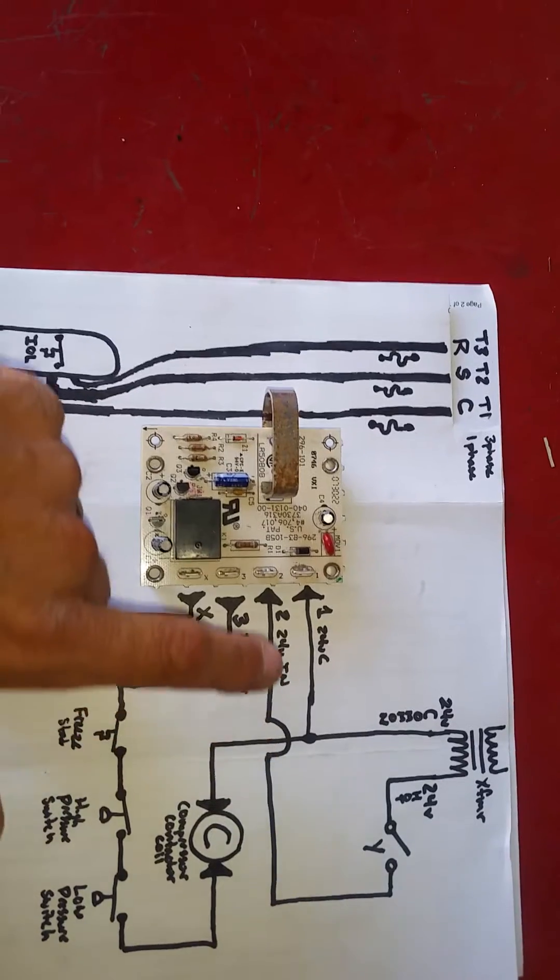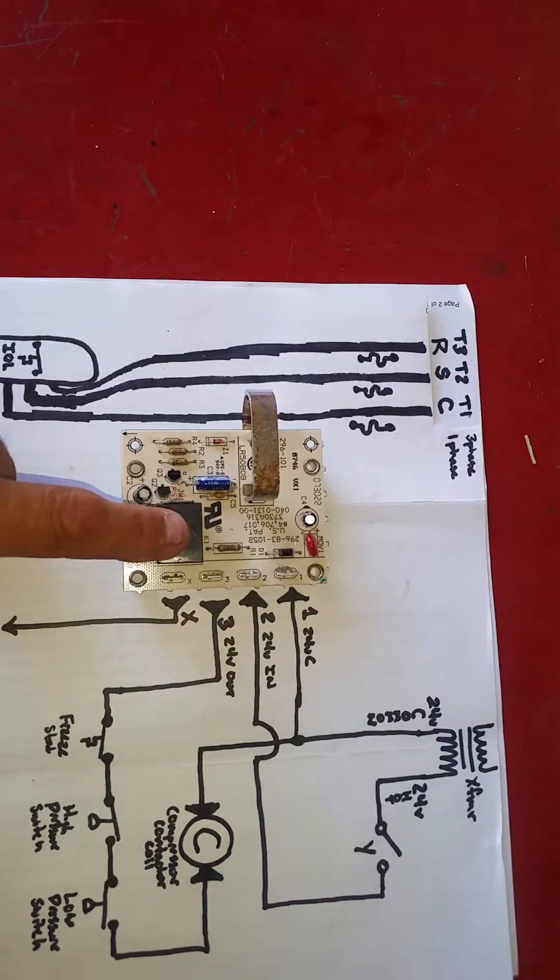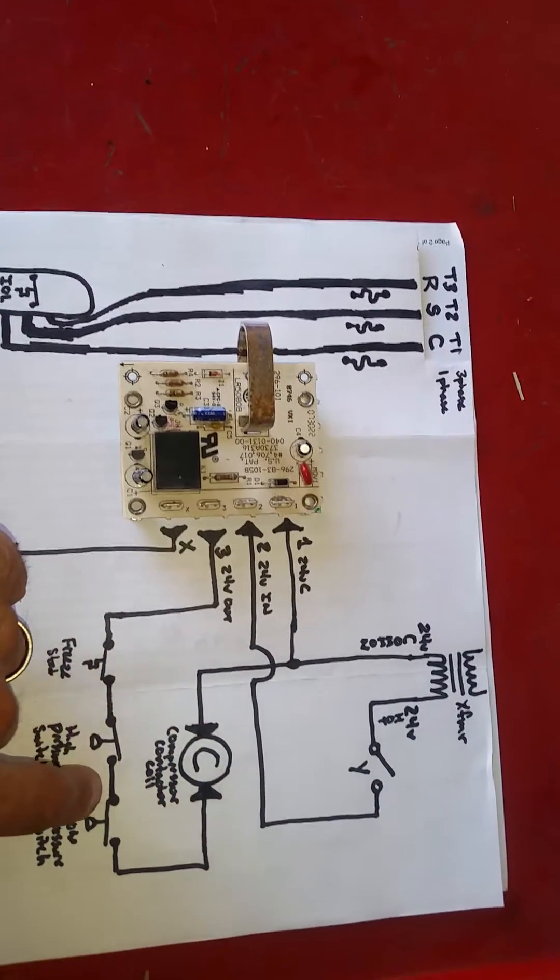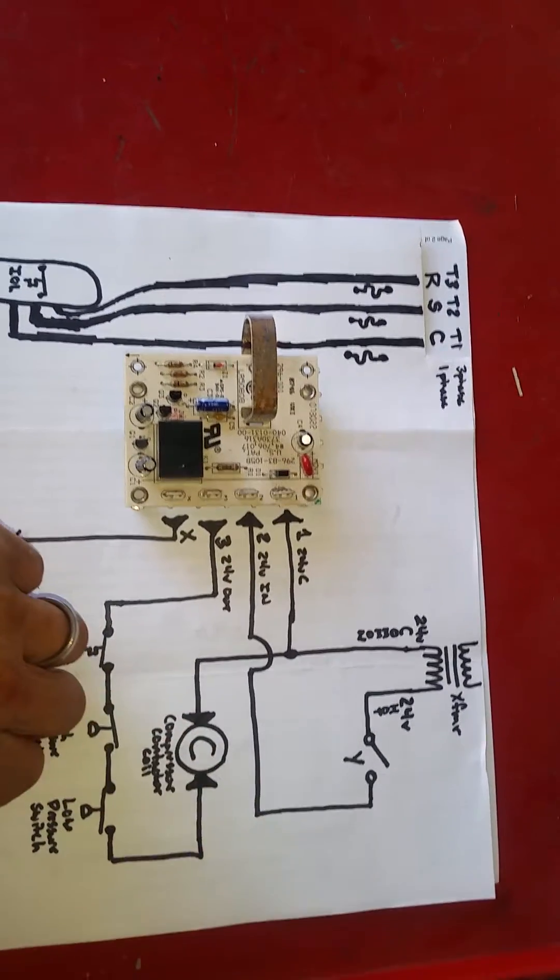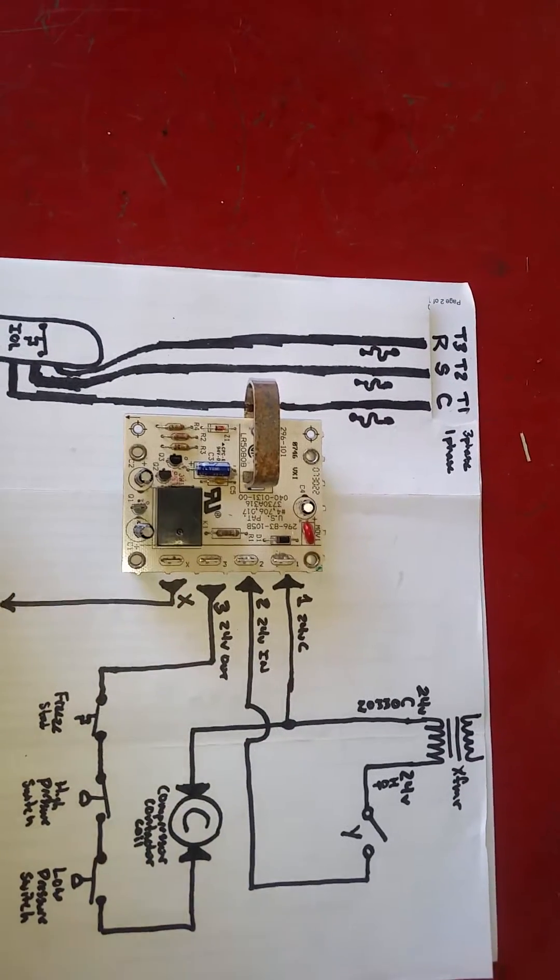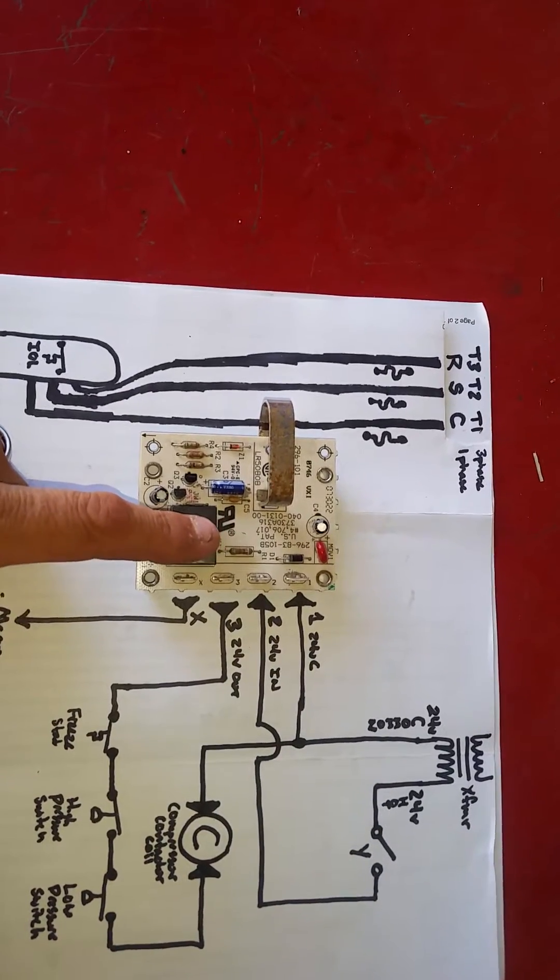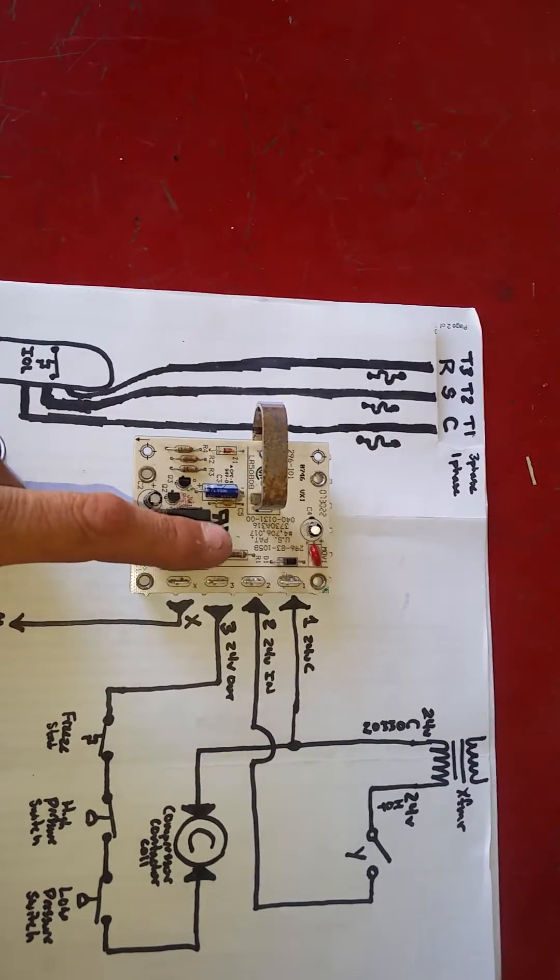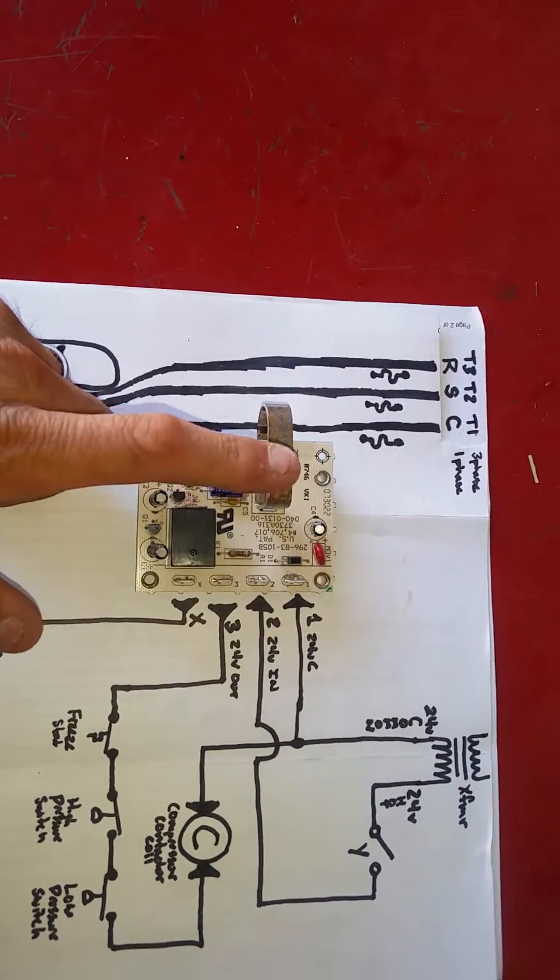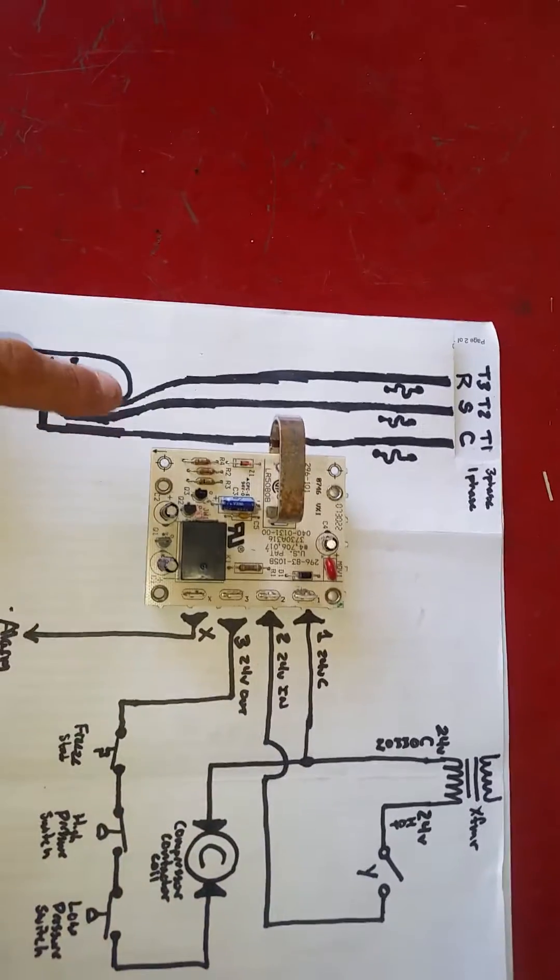So when 24 volts enters pin two, 24 volts is sent directly out to pin three via this normally closed relay, and goes through each of the safety switches in series, and energizes our compressor. This is the key of this board. The reason why I call this a current lockout board is that this board is required to see at least 2.5 amps through this current sensor within three seconds of the compressor contactor closing and the compressor starting.